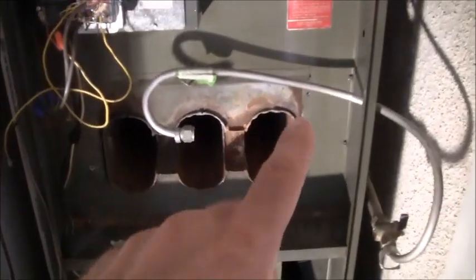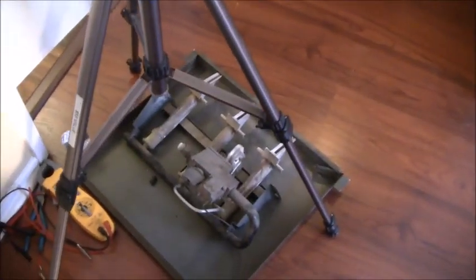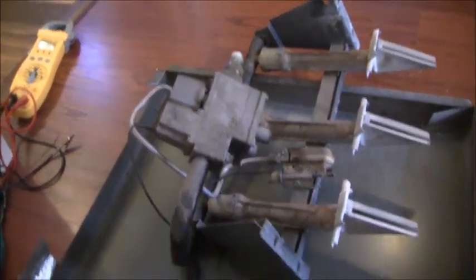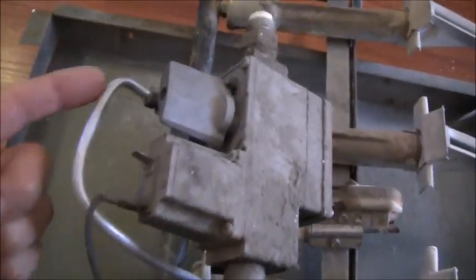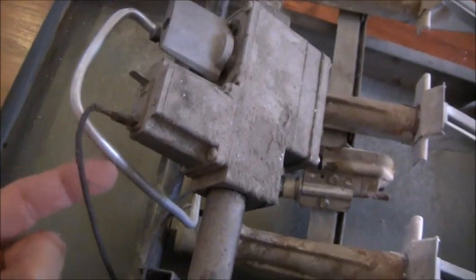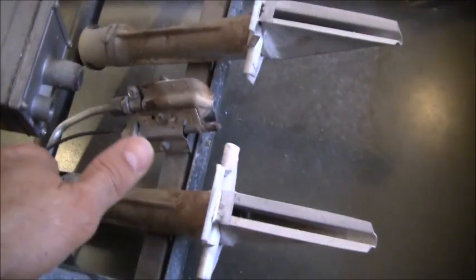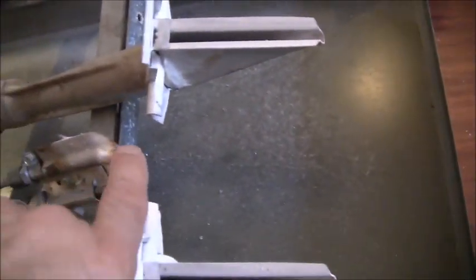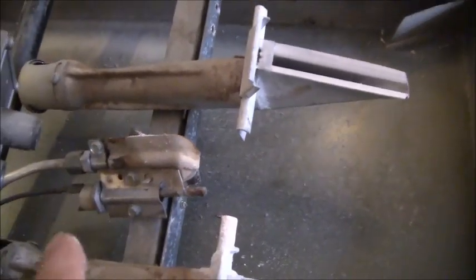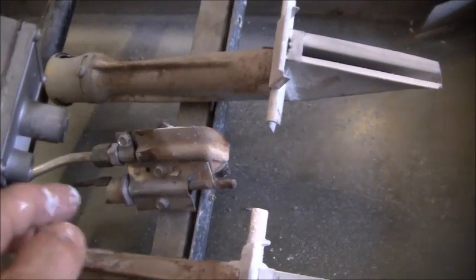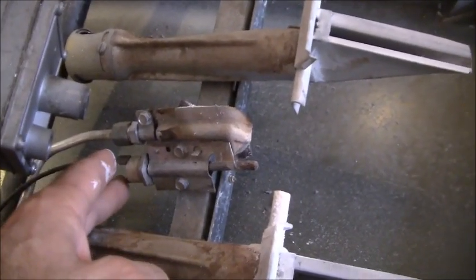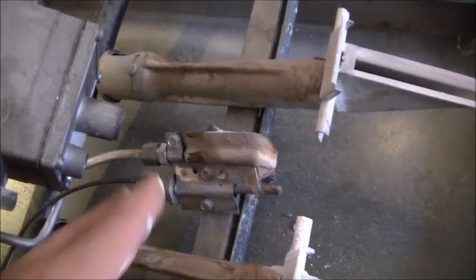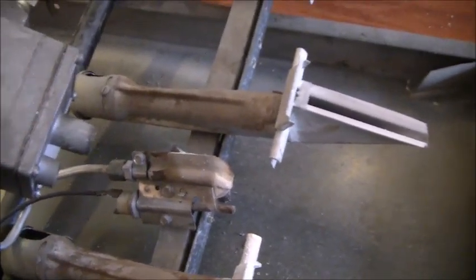Okay, the burner tubes are 100%. I'm ready to put these back in. While this is out, we should take a look at the thermocouple. Okay, so looking at this is your pilot right here. Your pilot flame comes down to this section right here where it comes out. And this is the thermocouple. There's normally two leads that go to the thermocouple. I have one of the leads disconnected so I could pull this assembly out.